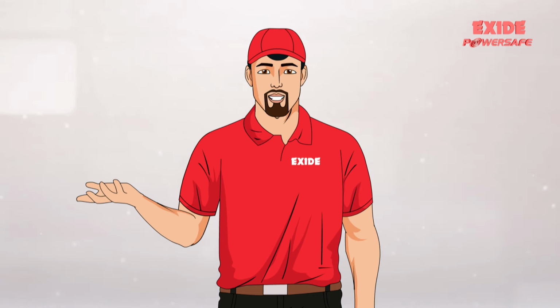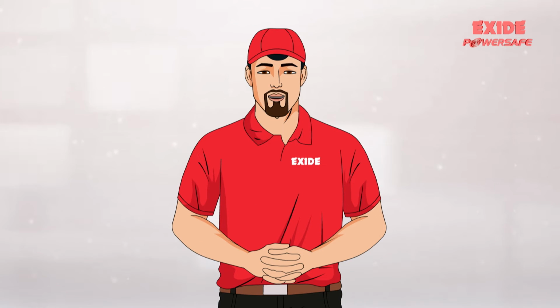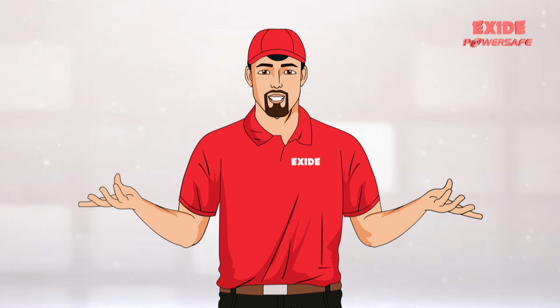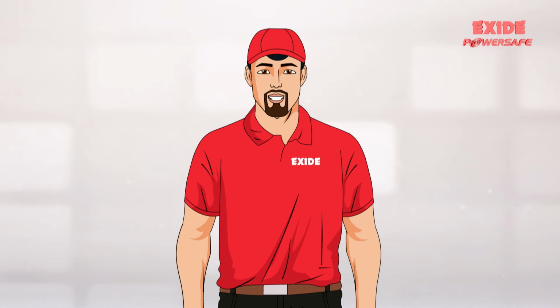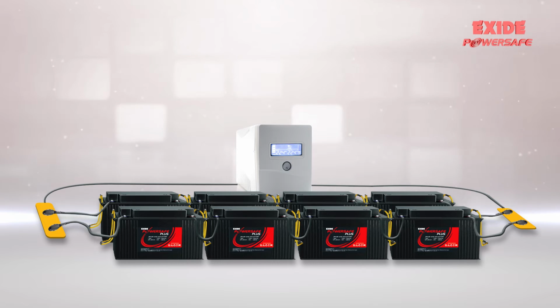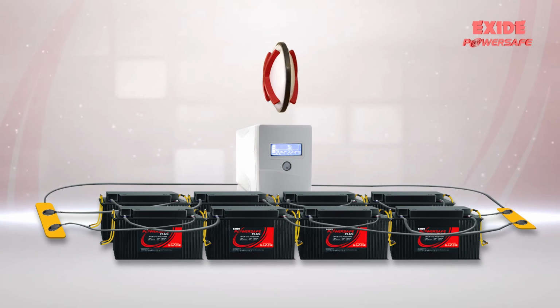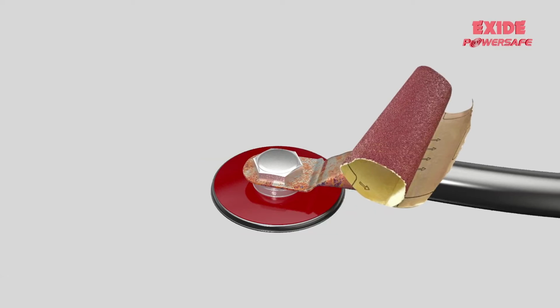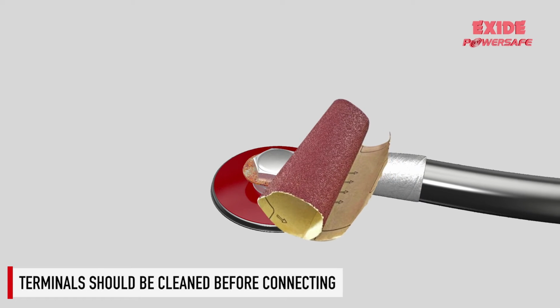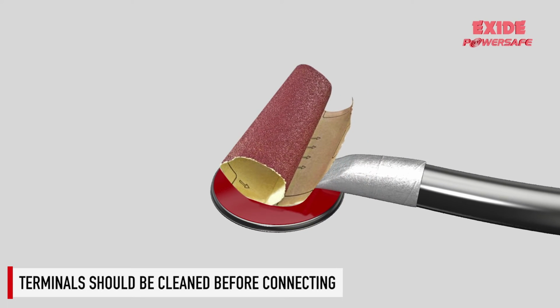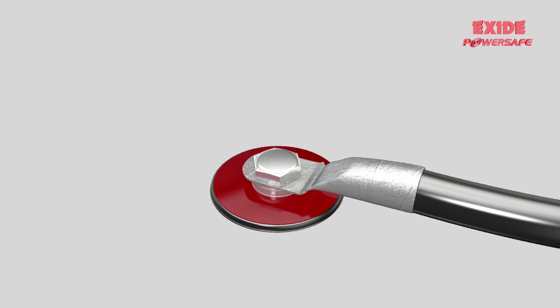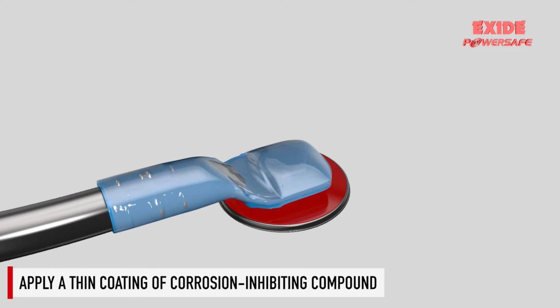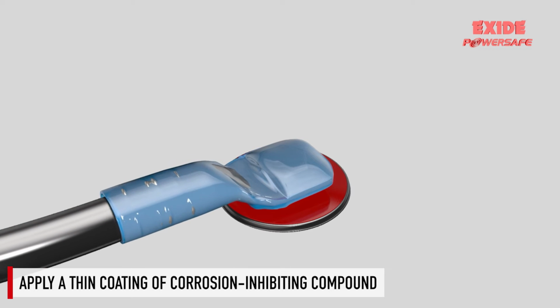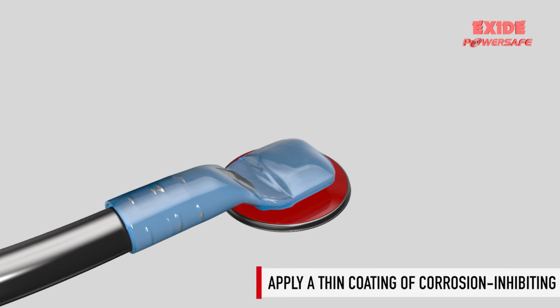Connecting batteries once they are mounted is a very important step to ensure proper functioning. These steps will help ensure that the connecting procedure is done without any fault. Batteries should be connected with proper polarity. Connecting with reverse polarity may damage the battery charger. All terminals should be cleaned before connecting the interconnecting cables with the help of zero emery paper. Post-connection, apply a thin coating of corrosion-inhibiting compound to the area.